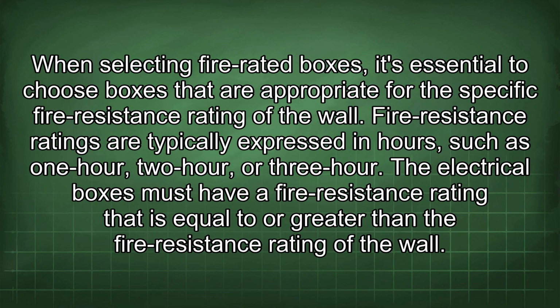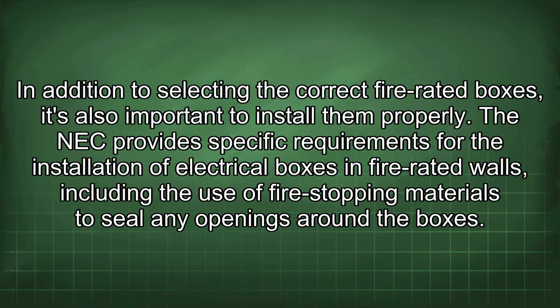When selecting fire-rated boxes, it's essential to choose boxes that are appropriate for the specific fire resistance rating of the wall. Fire resistance ratings are typically expressed in hours, such as 1 hour, 2 hour, or 3 hour. The electrical boxes must have a fire resistance rating that is equal to or greater than the fire resistance rating of the wall. In addition to selecting the correct fire-rated boxes, it's also important to install them properly. The NEC provides specific requirements for the installation of electrical boxes in fire-rated walls, including the use of fire-stopping materials to seal any openings around the boxes.